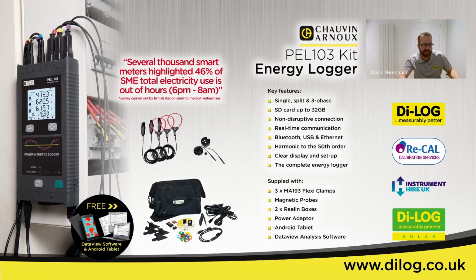If you're using a tablet within Bluetooth proximity of the instrument, you can easily look at the vector diagram, which gives you an idea and lets you check that all the phases are in the correct order, and that you haven't reversed the phases. There are indications on the front of the instrument to tell you if you've got the CTs around the wrong way, which is very common. As Pete said earlier, the arrow on the side of the CT points towards the load. That's an important statement - I've been to site many times to set these up or help people set them up, and it's an easy mistake to make.